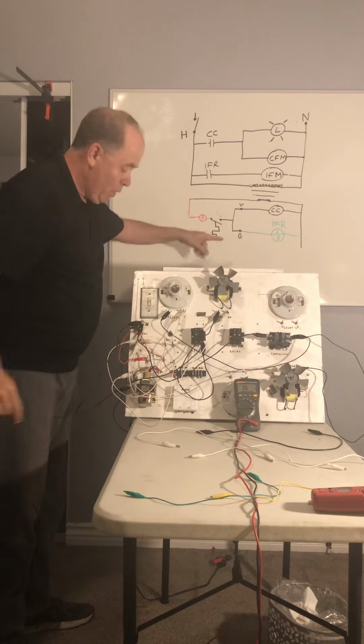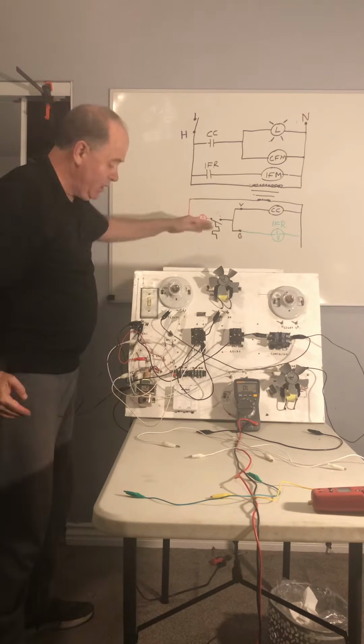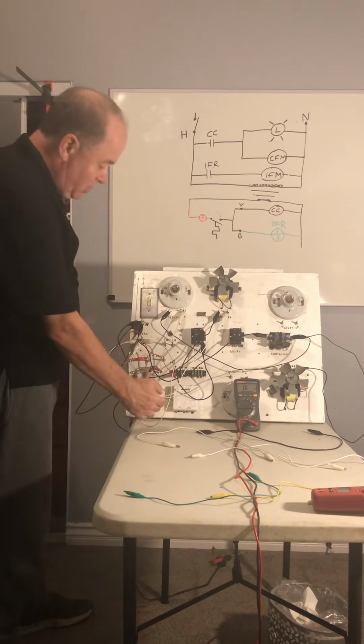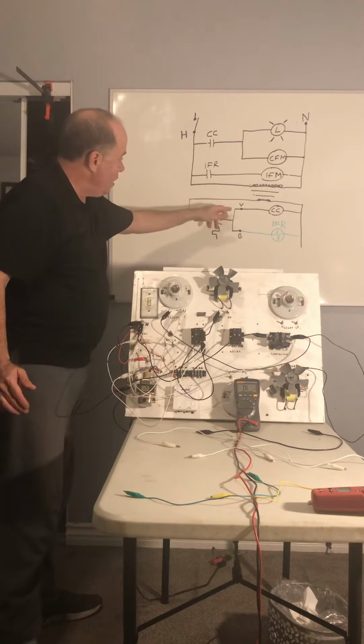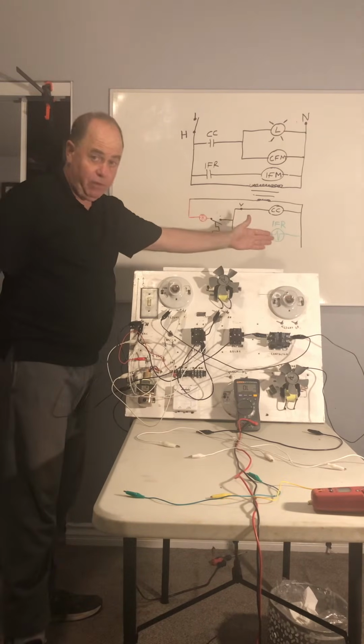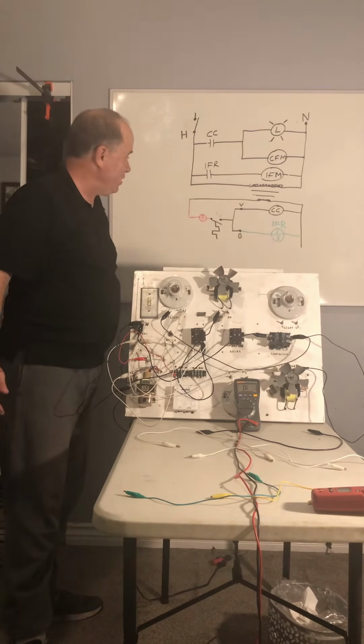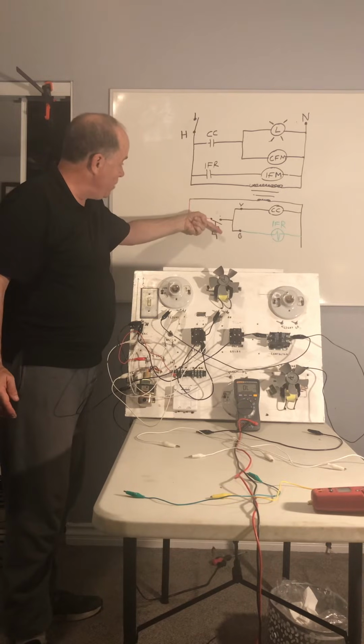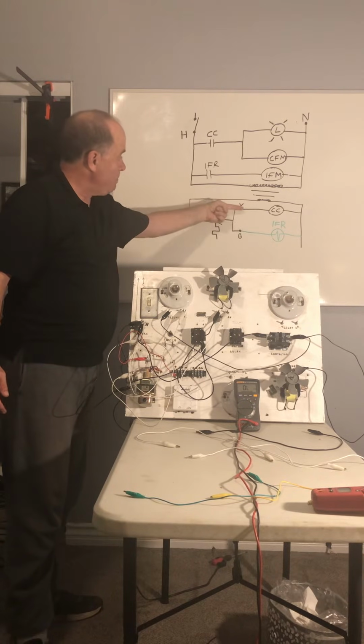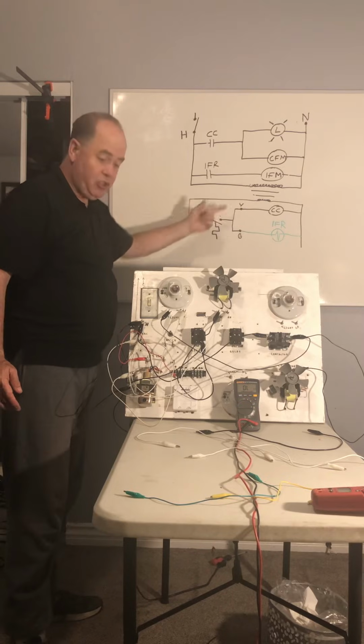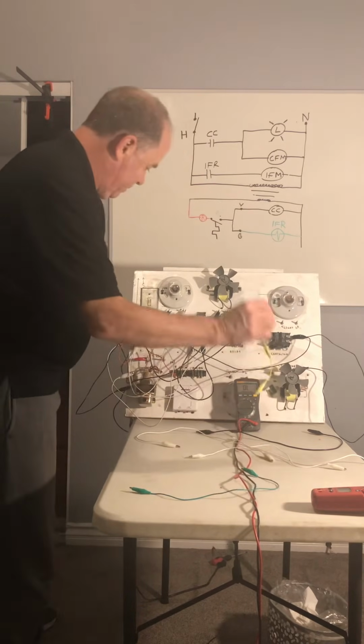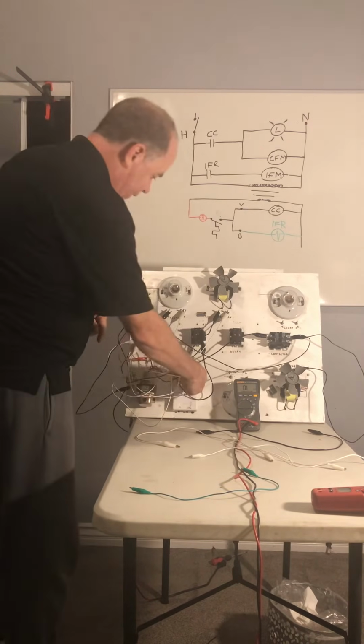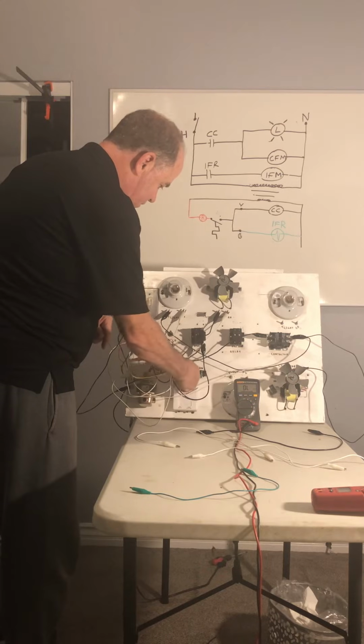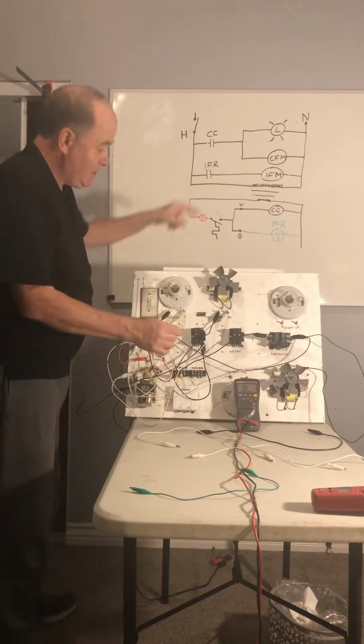And then when the thermostat closes on cooling, and the fan switch is in auto, we want to run the indoor fan, or evaporator fan, with the compressor and the condenser fan motor. So when it gets warm enough and this closes, we power up Y, which is typically run with a yellow wire off of the Y on the thermostat to the contactor coil.